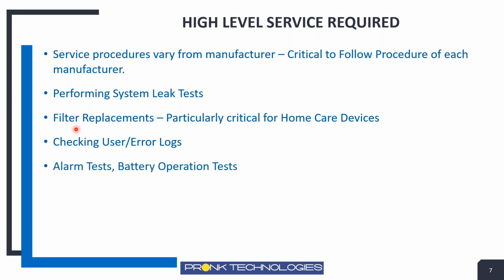Alarm tests, we'll talk about that, and you'll see an example of how critical alarm tests are. Battery operation tests, we talk about battery operated devices. There were a number of incidents where the batteries failed to operate when power went out, or they were running on batteries, and it caused patient incidents to occur because the battery was not maintained at the proper intervals. And of course, we need to do our flow and pressure tests.